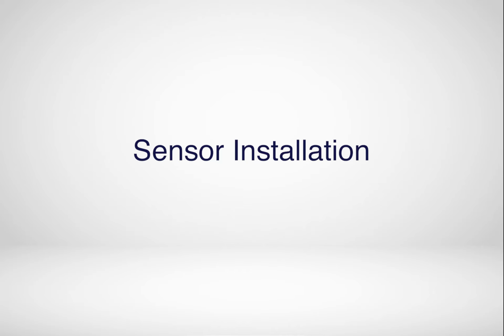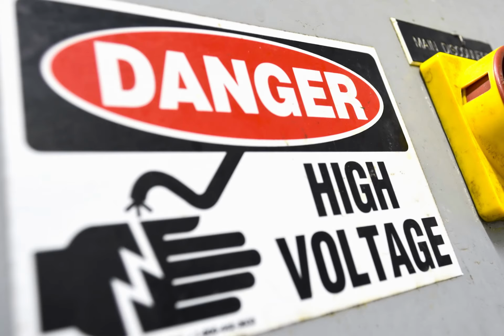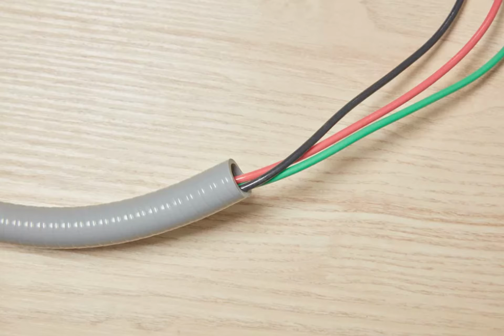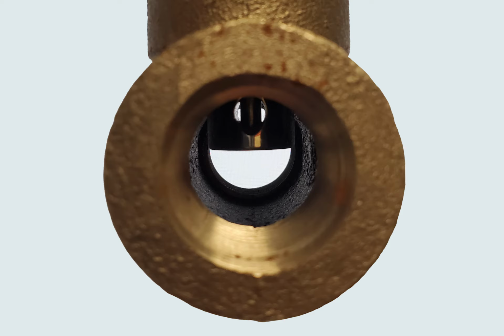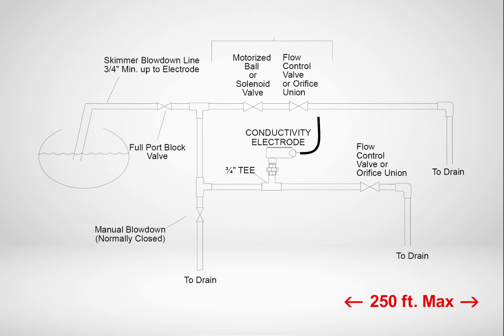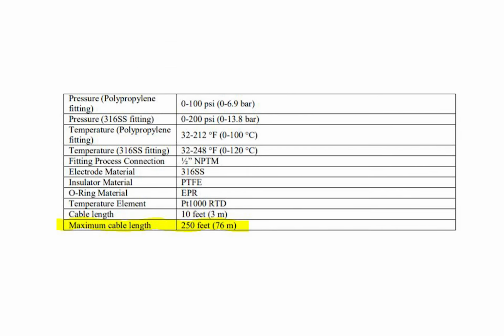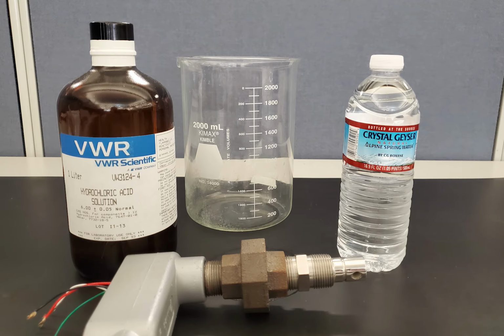Here are the do's and don'ts regarding sensor installation. Do not run sensor wires near high voltage lines or VFDs. Do not run wires in conduit with other wires. Make sure the hole in the sensor is in line with the piping for best results. All sensors have a manufacturer's maximum distance. Make sure you do not exceed these values. For a Walchem boiler sensor, it can go up to 250 feet maximum. Clean the sensor periodically as needed, or at a minimum once per year.